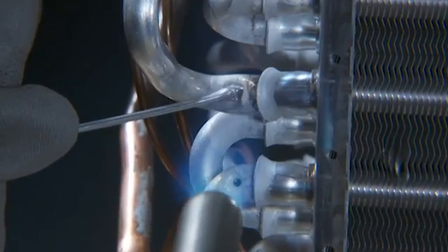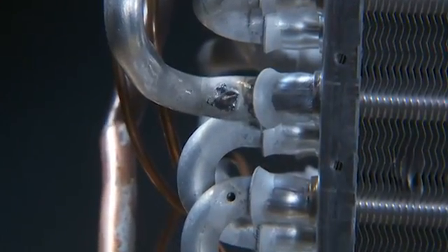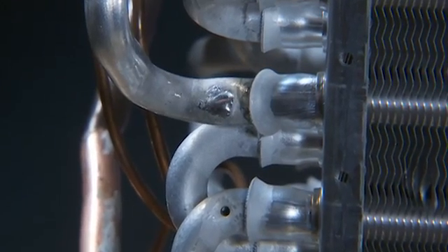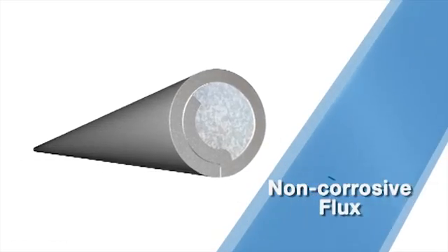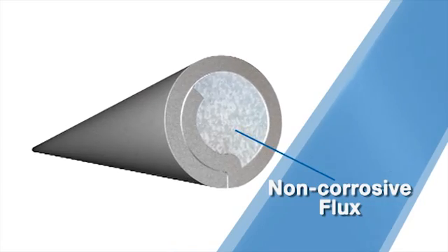Because HandyOne AL822 is a flux-cored braze alloy, additional flux is not needed. A non-corrosive flux is built in, right inside the center of the rod.